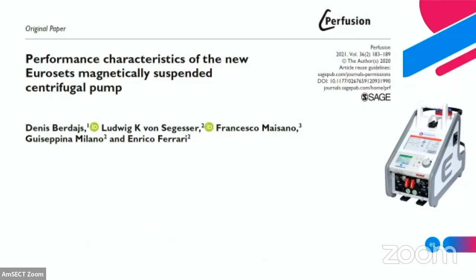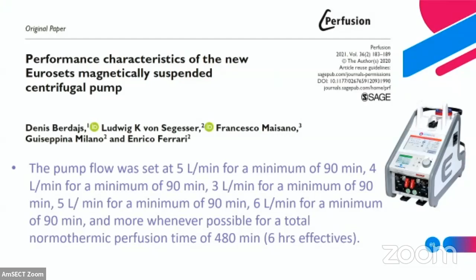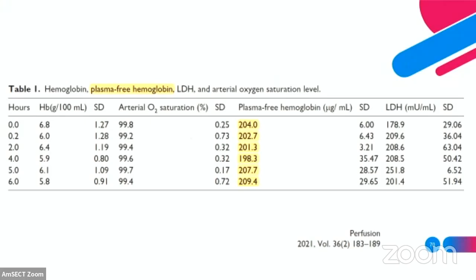It was tested with a set flow of 5 liters per minute for 90 minutes, 3 liters per minute for another 90 minutes, and back to 5, and at the end 6 liters per minute, always for 1.5 hours. And what happened to the blood of our patient? The plasma-free hemoglobin still remained inside the acceptable range. You can see here in the table that summarizes the results.